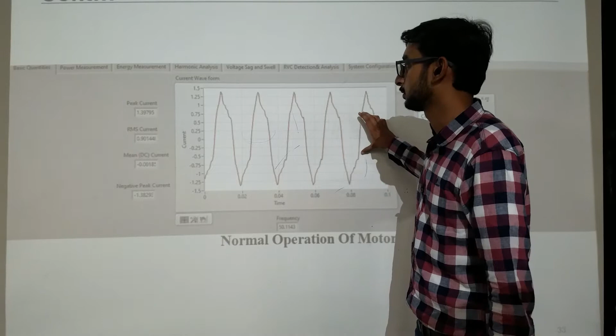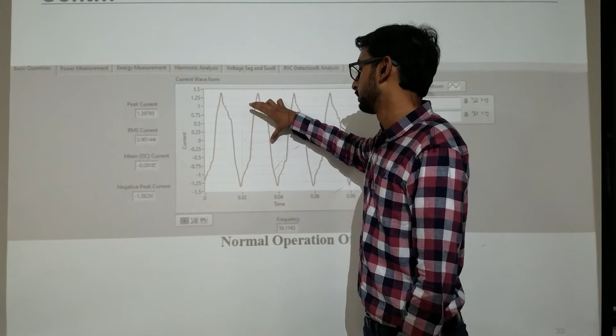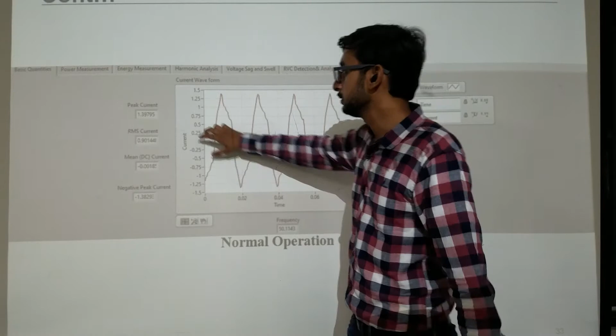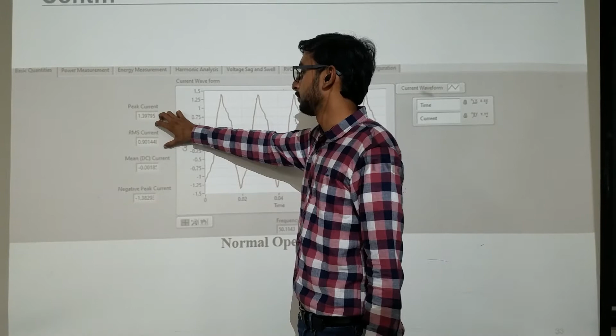This is the normal operation of our motor. The waveform is basically a little bit distorted. As you can see, there is the previous result. In operation, as you can see, the peak and RMS decrease by 3 times because the inrush current has already passed with time, and now it's operating in a normal condition.